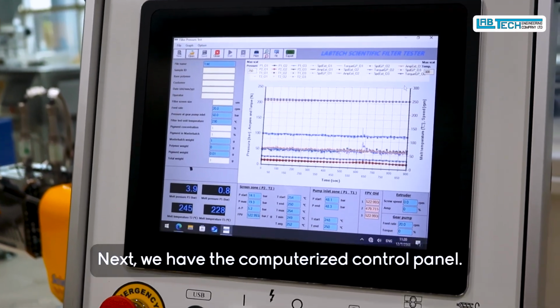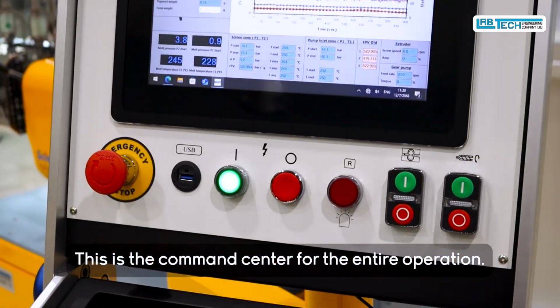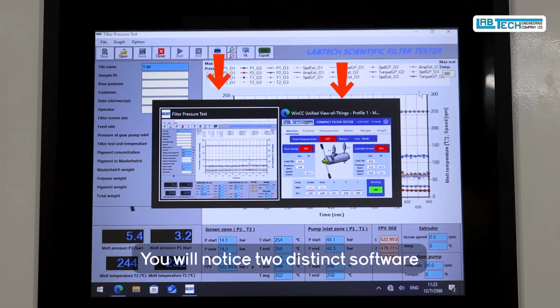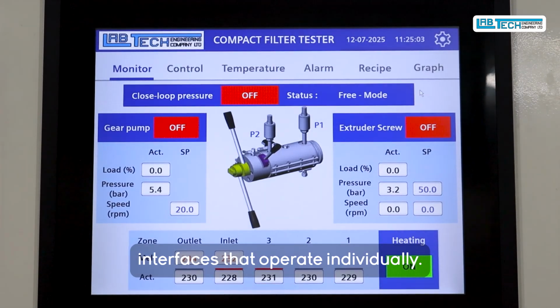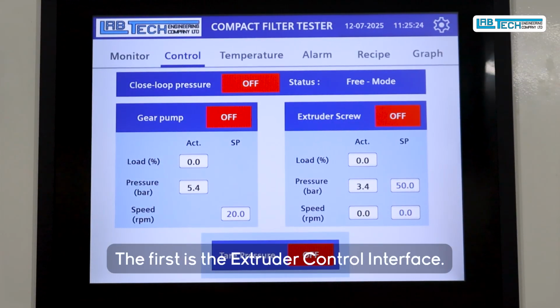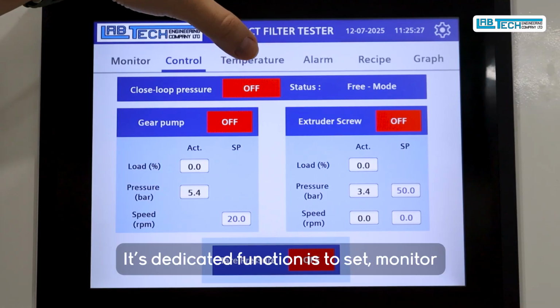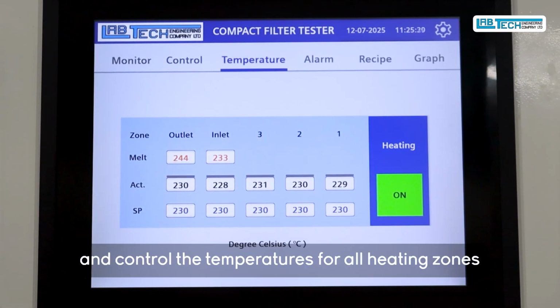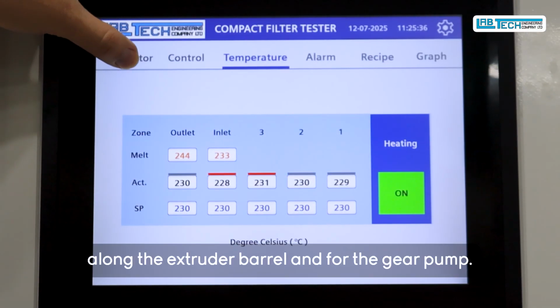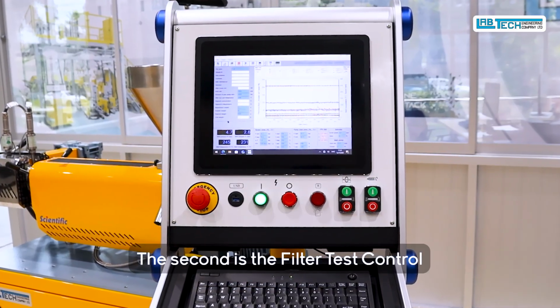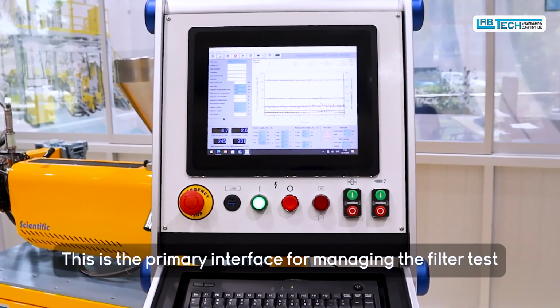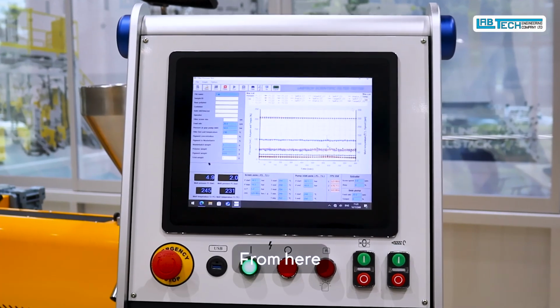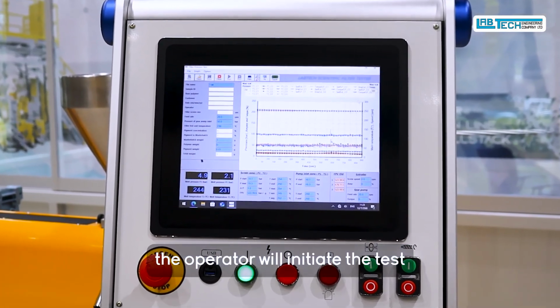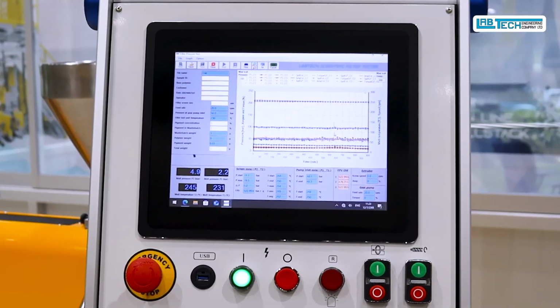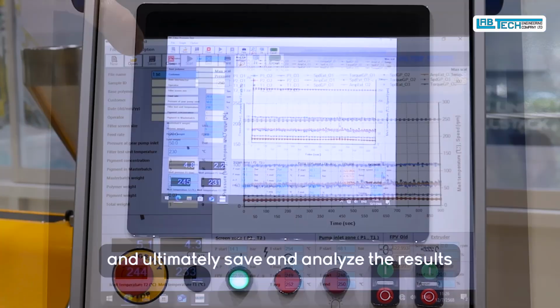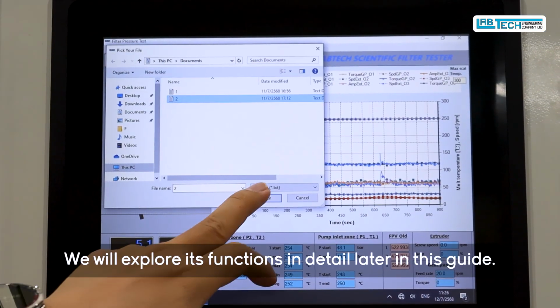Next, we have the computerized control panel. This is the command center for the entire operation. You will notice two distinct software interfaces that operate individually. The first is the extruder control interface. Its dedicated function is to set, monitor, and control the temperatures for all heating zones along the extruder barrel and for the gear pump. The second is the filter test control. This is the primary interface for managing the filter test. From here, the operator will initiate the test, monitor the real-time graphical data, and ultimately save and analyze the results. We will explore its functions in detail later in this guide.